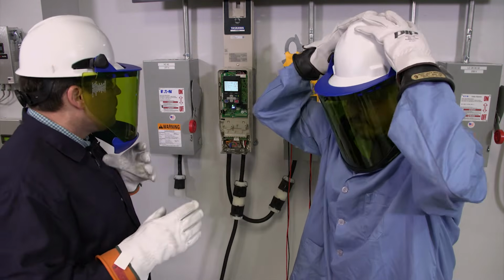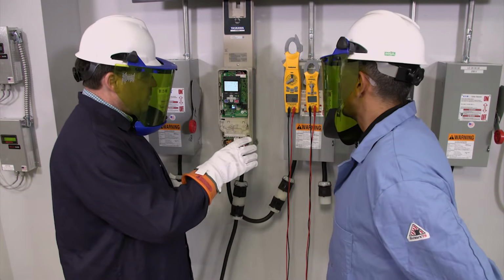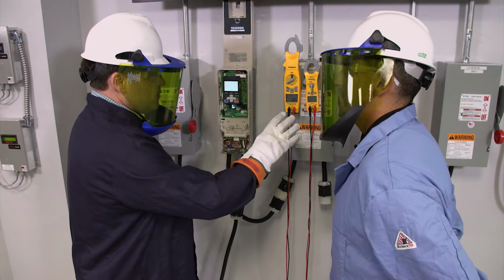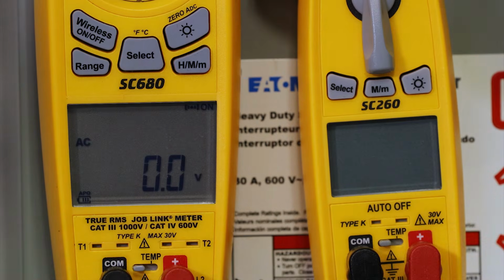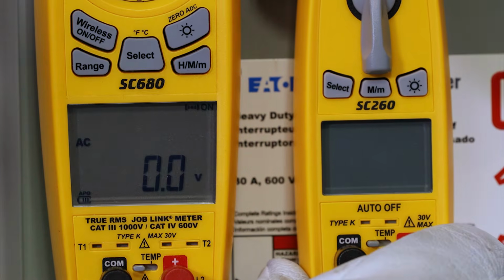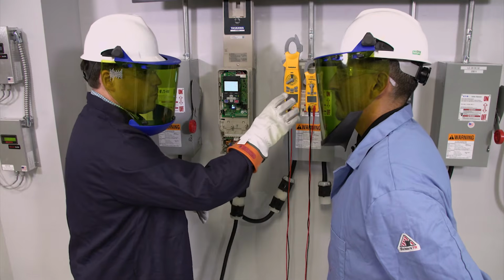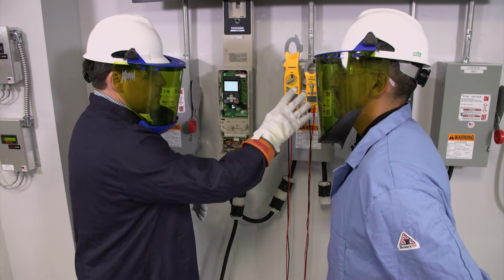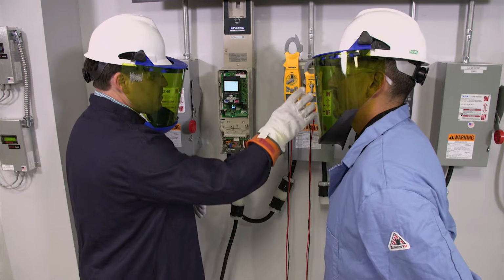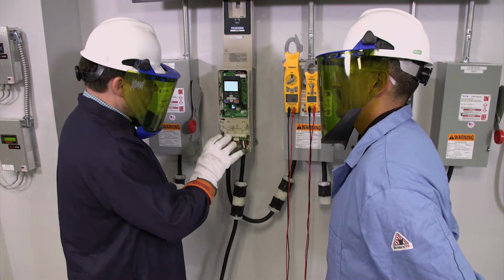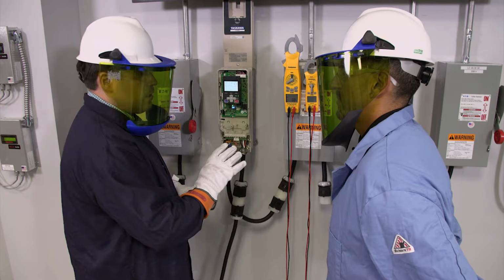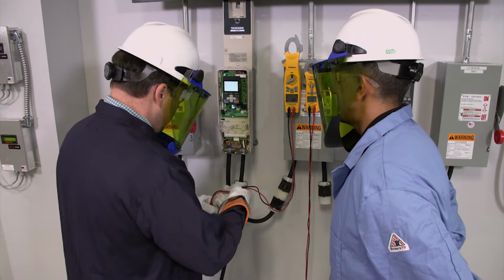The first thing we're going to do is use each one of these meters. We have an SC680 here with filtering, and an SC260 meter, which is more geared for residential and light commercial use. It doesn't have the filtering capability, but it's still a very capable meter. We're going to measure the entering side of this VFD first, starting with the 680.